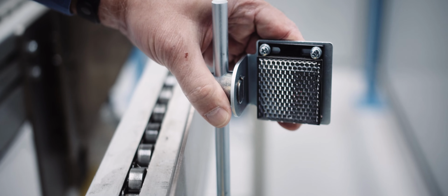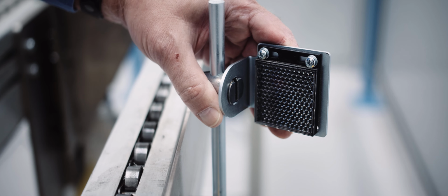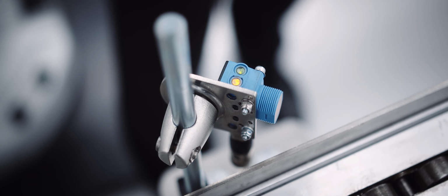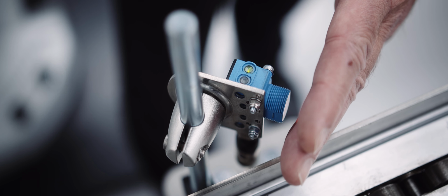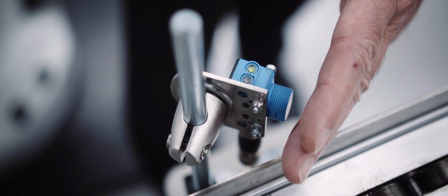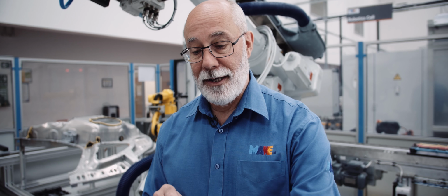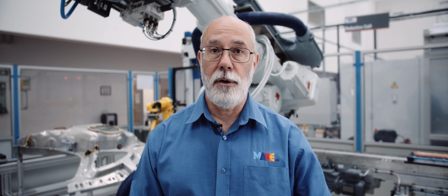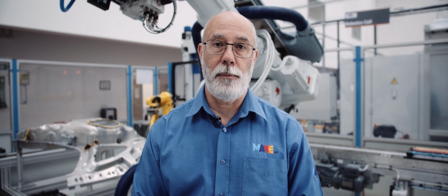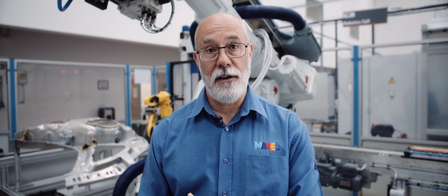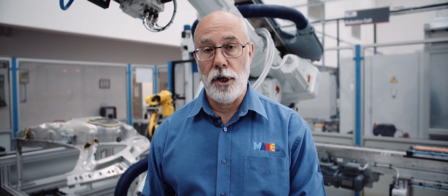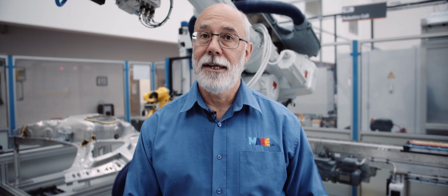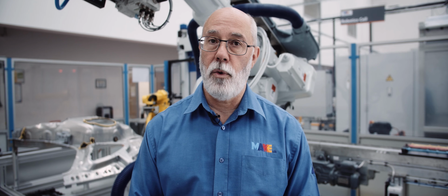So the first thing I'm going to do is reposition it, make sure I've got a sensor light here, which I now have. If I put my hand in the way, it interrupts it, so I know the sensor is working. The next thing I'm going to do is tighten that back up again, make sure it's secure. The additional thing I'm going to do is make people more aware of where that reflector plate is for anybody who works there in the future. Everything's now secure. I'm going to go back out, make the cell ready to use, and do a full functional test to make sure it works as it should.